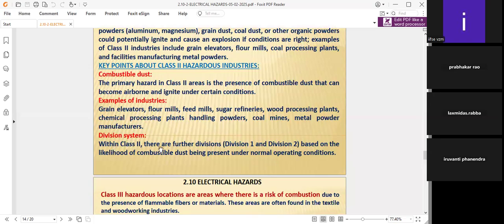Within class 2, there are further divisions, division 1 and division 2, based on the likelihood of combustible dust being present under normal operating conditions. If you go through the literature of class 2, which closely follows the literature given by the standards, there are further divisions, because some dusts ignite immediately, and some dusts take some time and ignite after some more time. That means division 1 means ignited immediately. That will be taken care of.